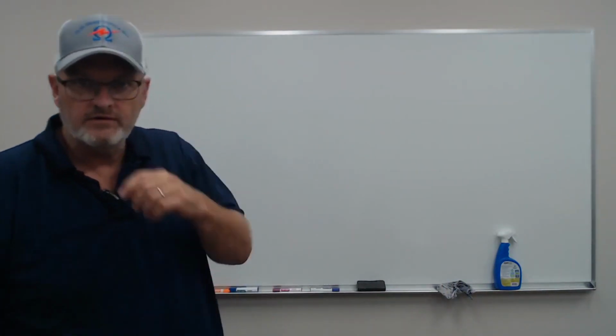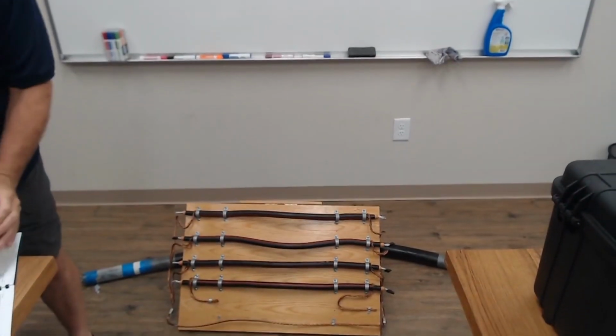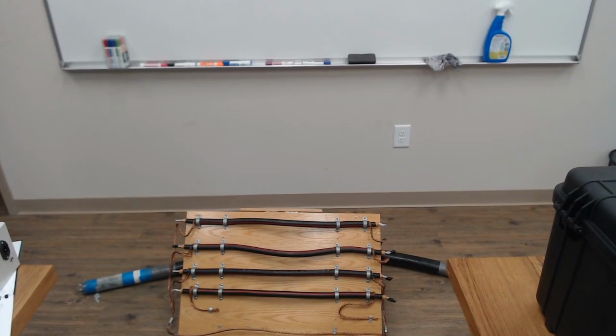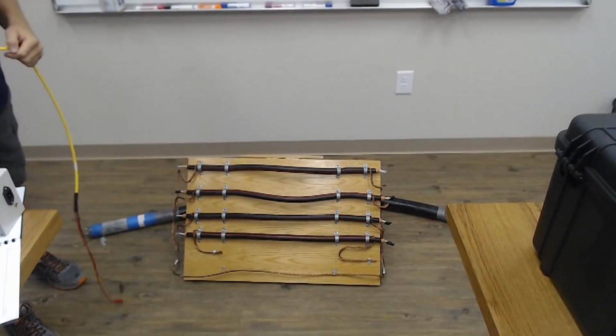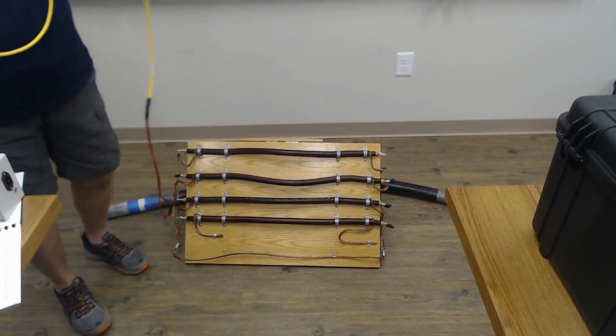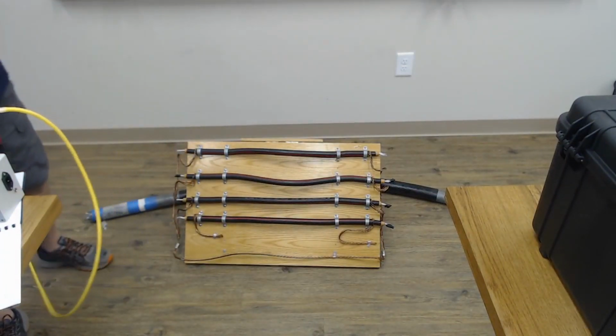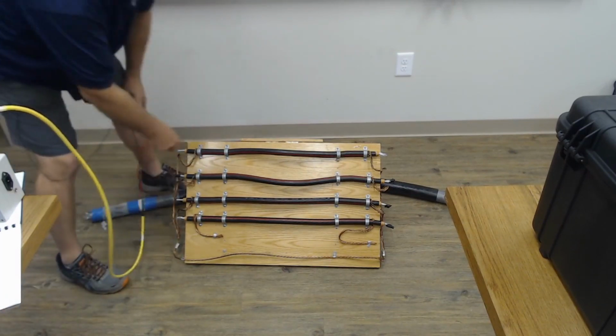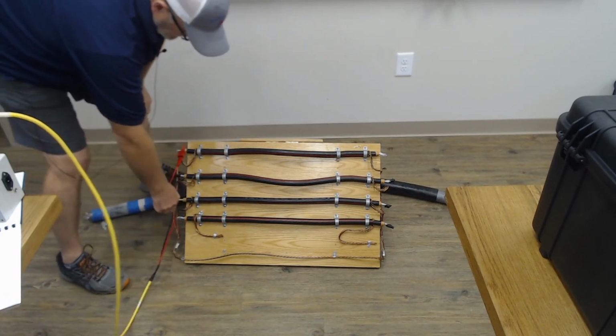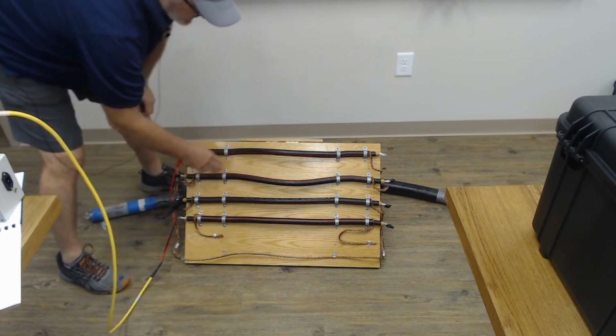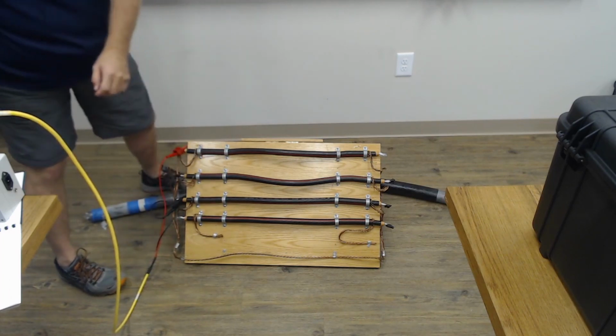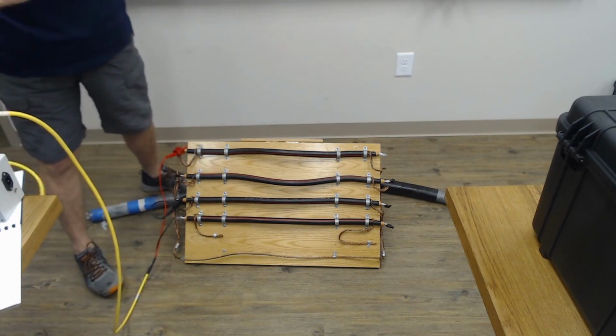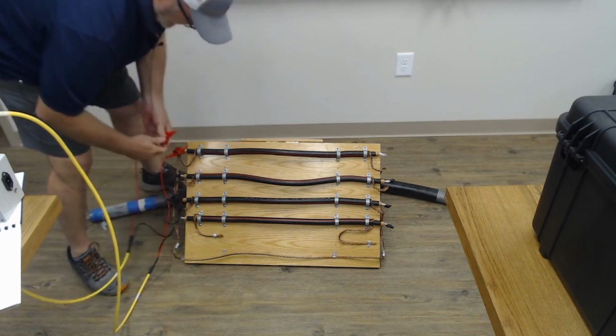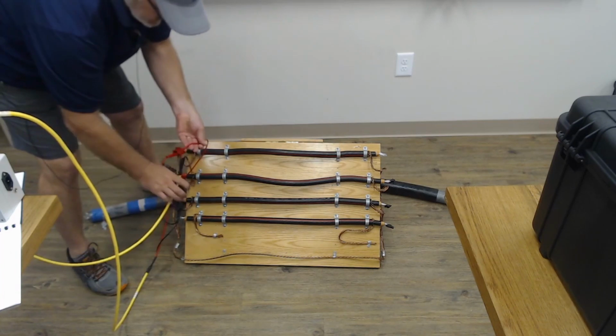So next we'll do the hookup. We're going to do a direct connection first. So Cody, if you can shine down on this board over here. And what we're going to be doing is connecting A phase that we're going to be hooking up onto the one side of the cable. So we'll call this guy over here L1, and this over here will be our C phase. So this is A, B, and C phase, or L1, L2, L3. And likewise, we're going to hook on the other cable to black cable to C phase, and this one being L2 over here.